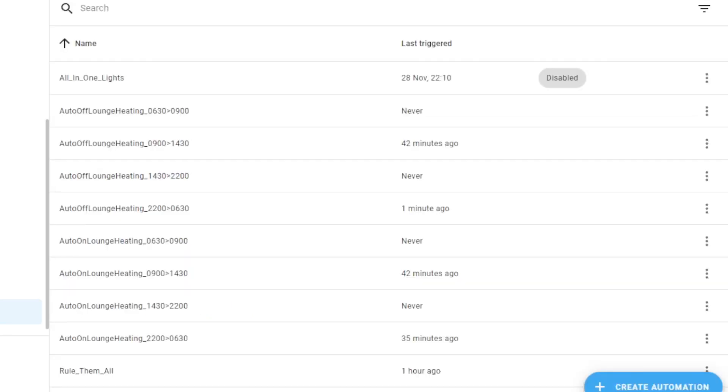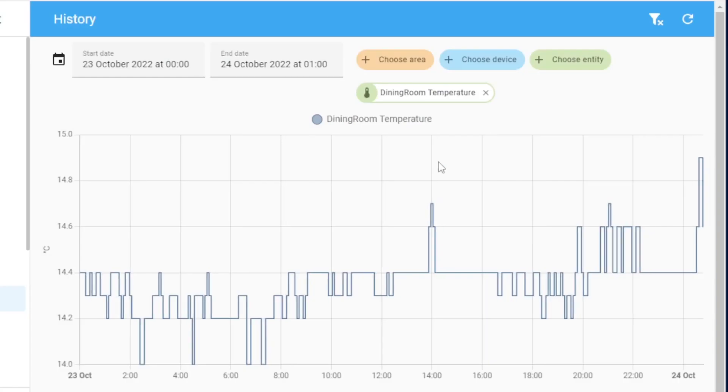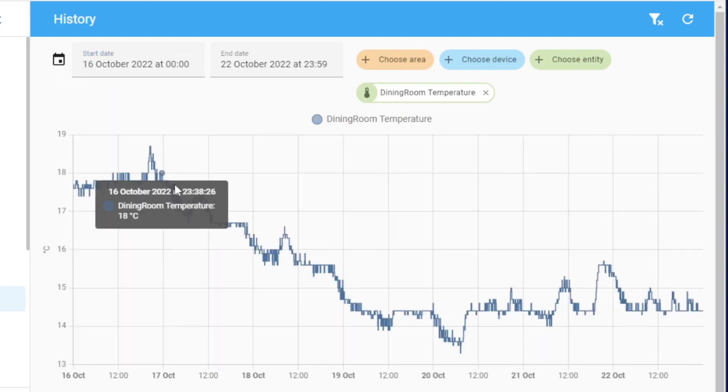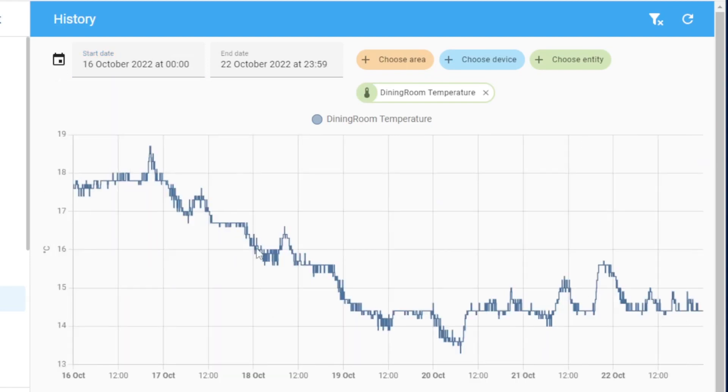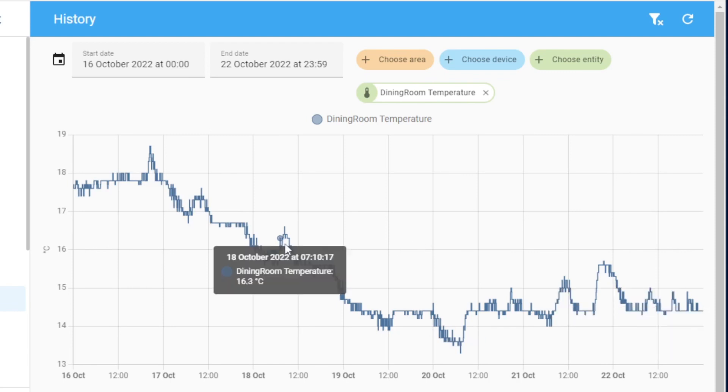Right, so I'll let you know how these run during the week. We can have a look at how the temperature sensor looks right now. So I am expecting things to look a little bit more stable. You can see, there we go, I mean we just basically had the heaters manually turned on and off, and one of the heaters wasn't even running at some point, because it has a thermostat on it. It's a very basic one, but it was turned quite low, and so nothing was running.